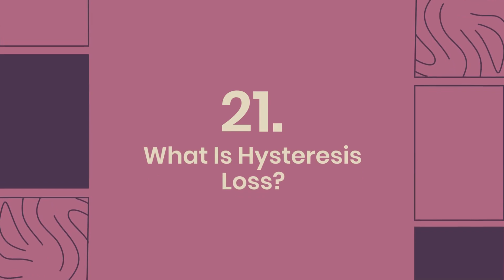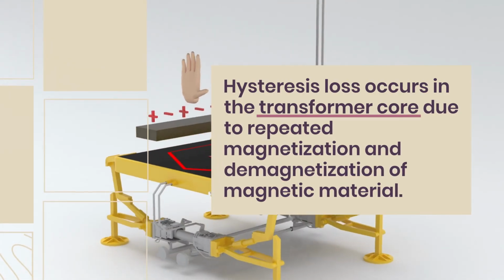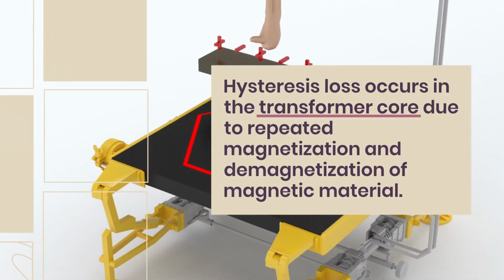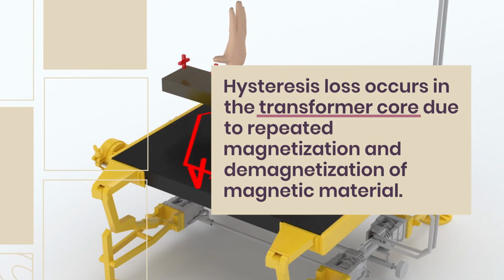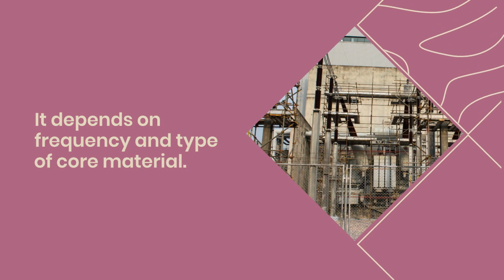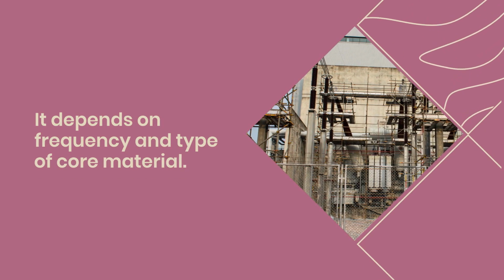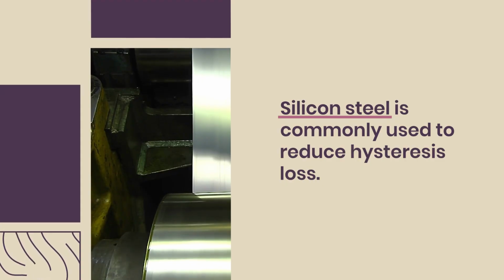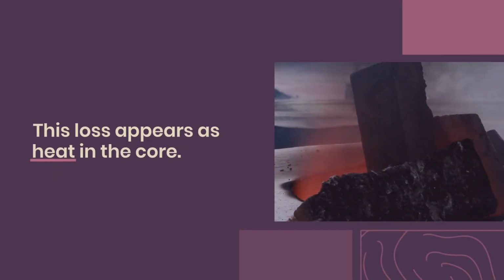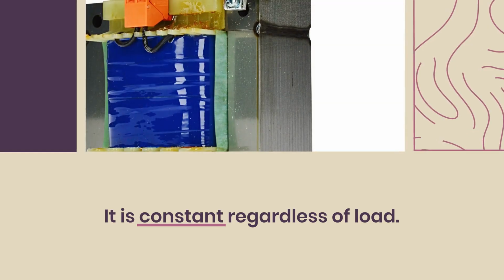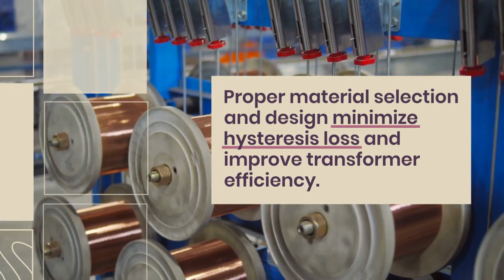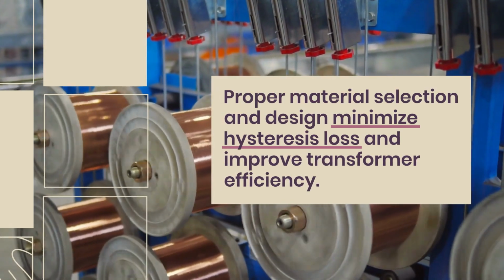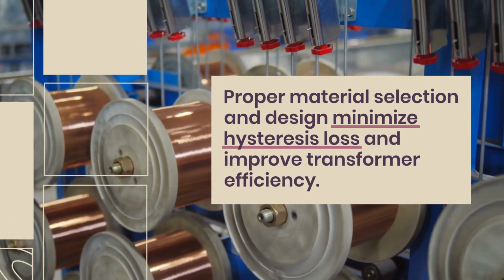21. What is hysteresis loss? Hysteresis loss occurs in the transformer core due to repeated magnetization and demagnetization of magnetic material. It depends on frequency and type of core material. Silicon steel is commonly used to reduce hysteresis loss. This loss appears as heat in the core. It is constant regardless of load. Proper material selection and design minimize hysteresis loss and improve transformer efficiency.